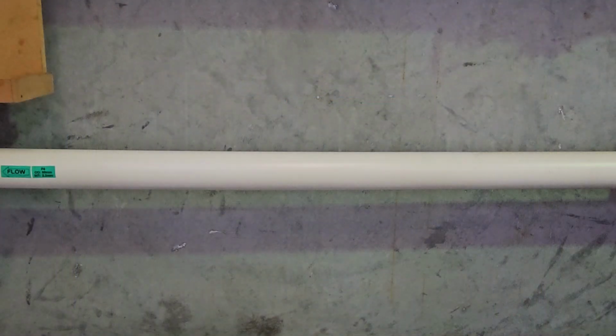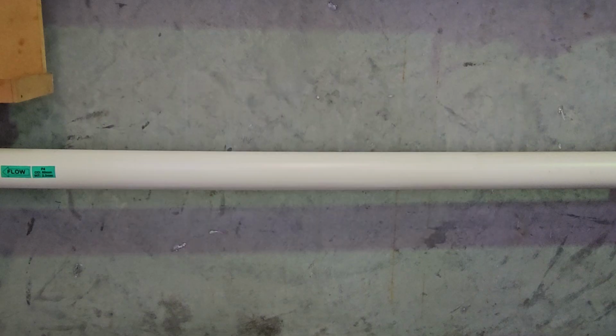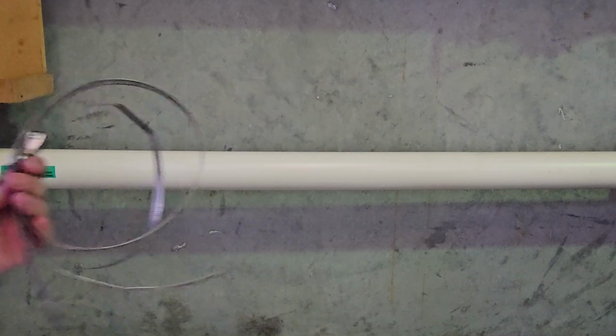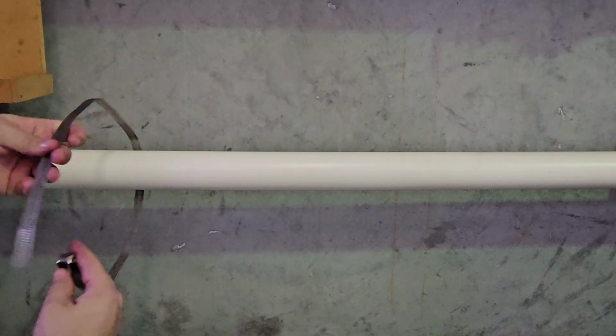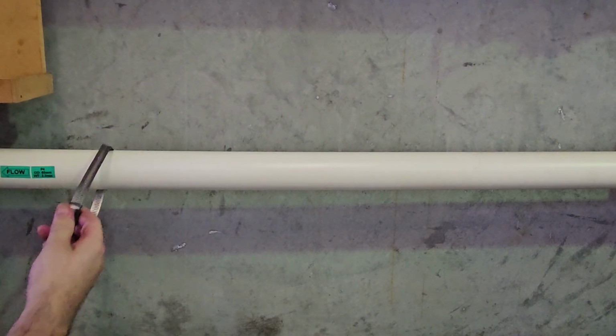With this distance in mind, prepare the sensor mounting area, clean or sand any dirt, rust, or paint to create bare pipework. In this case we have clean PVC. Now take the pipe straps and prepare them on the pipework, wrap them around the pipe and set up as much as possible to ease install of the sensors.